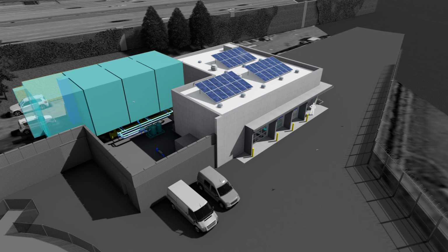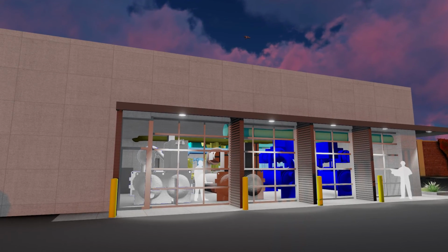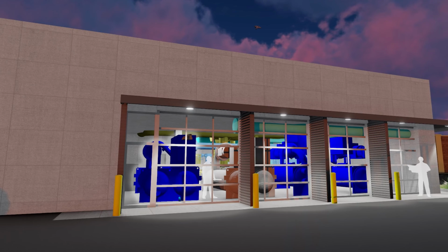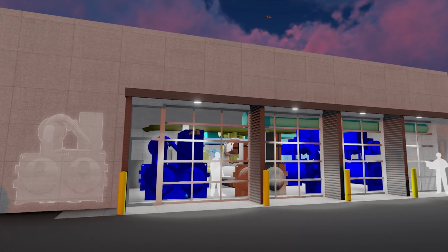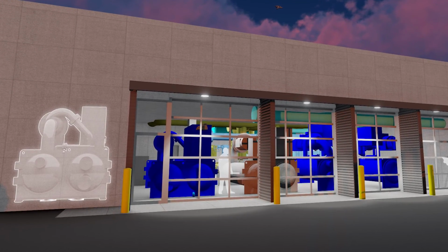The design minimizes shutdown of the existing central plant systems by keeping the existing modular chiller and associated cooling towers in operation while the proposed central plant is constructed. It provides ease of construction and phasing, as almost all the construction activities are dedicated to the south side of the central utility plant yard. This solution provides easy access for maintenance and operation, with increased clearances around the equipment. Our design also provides space for a 4th chiller and cooling tower with expansion capabilities in the future to add a 5th redundant chiller and cooling tower if needed.